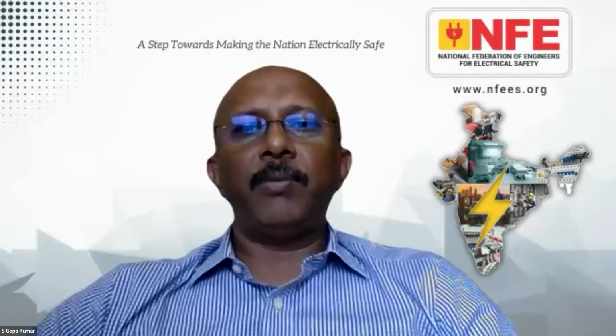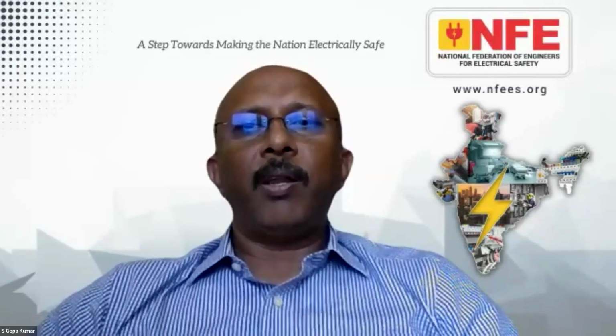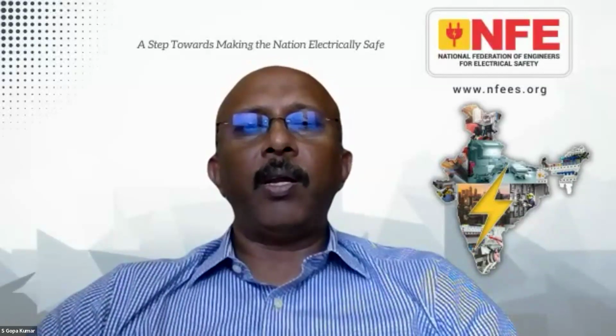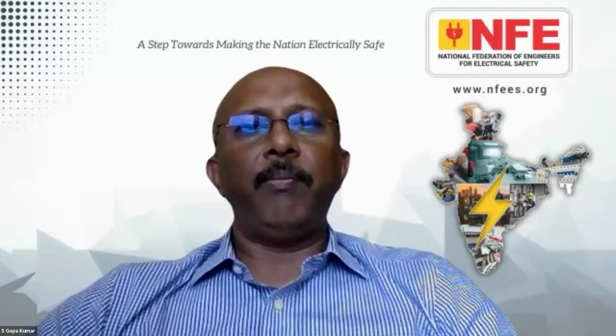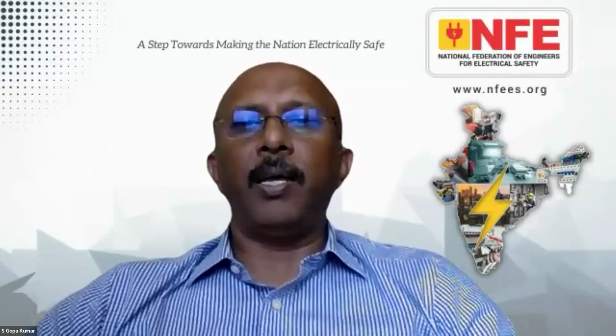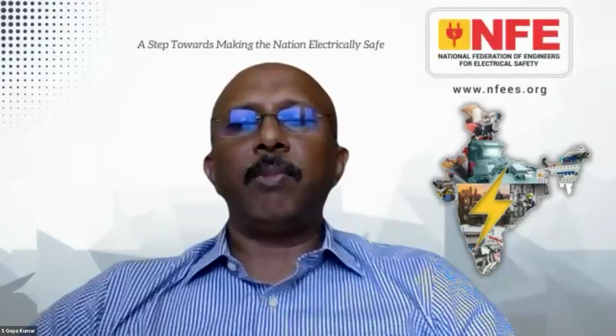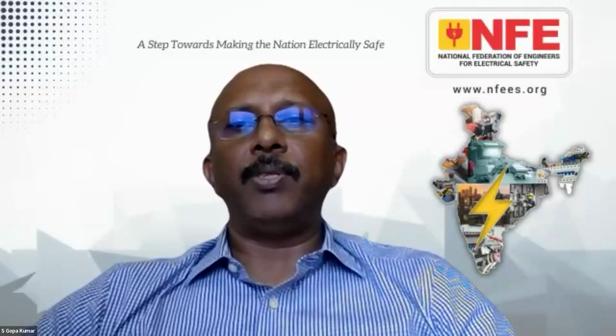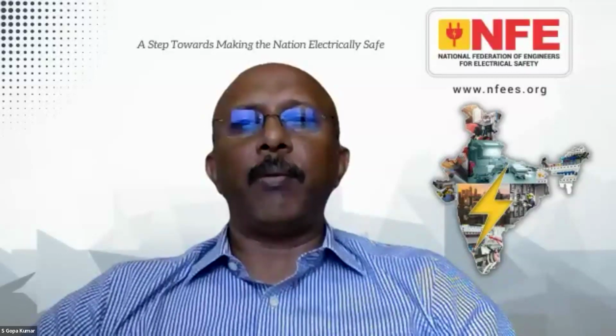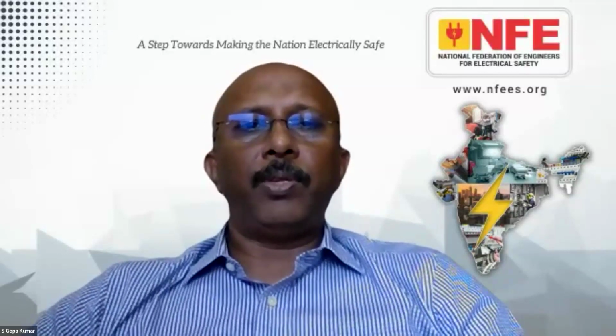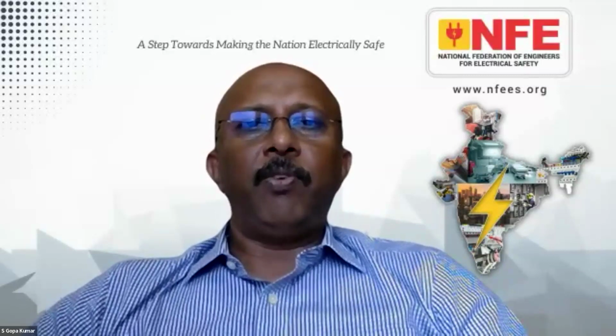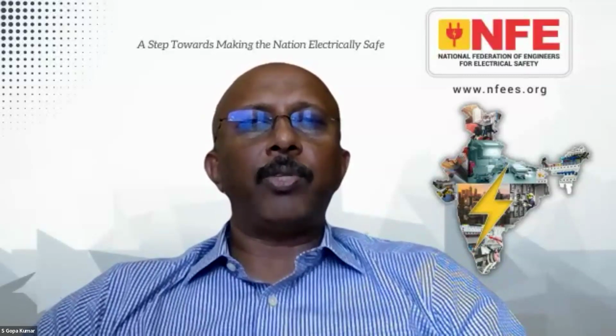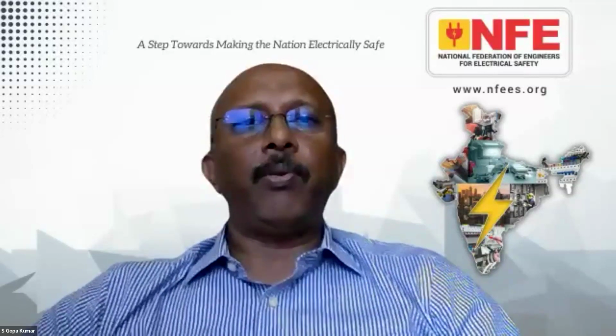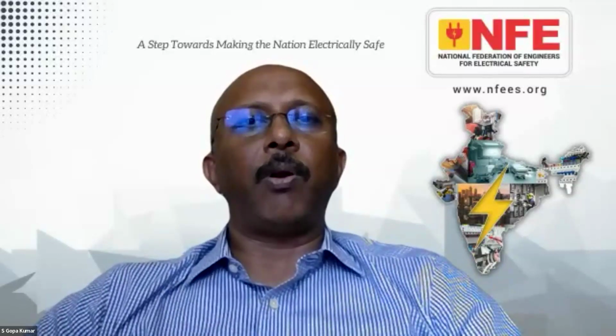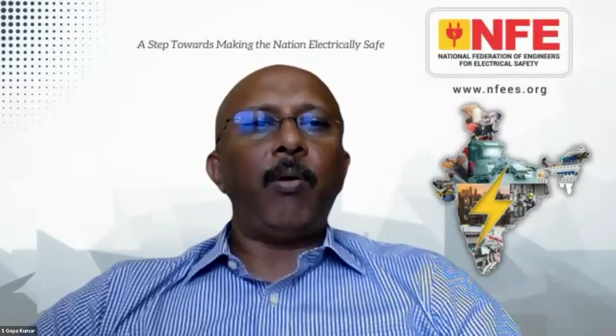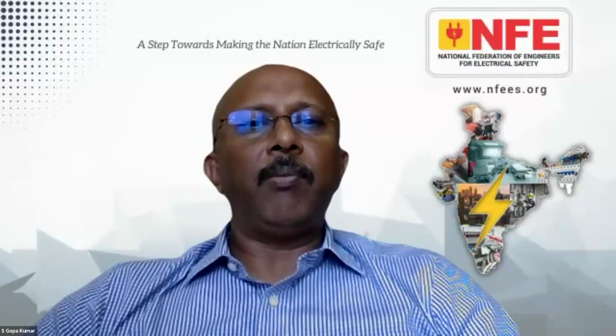You have a 250 amps MCCB, and the MCCB requires, let us say, X value of fault current and a certain value of impedance, and most of the time the impedance is high. The available fault current is much lower than the current which is required to disconnect within a short time. So this is what I'm always trying to stress: the maximum expected fault current. Of course, you have to size the conductors and the protective device based on the maximum expected fault current. But it is equally or more important that the protective device is able to trip.